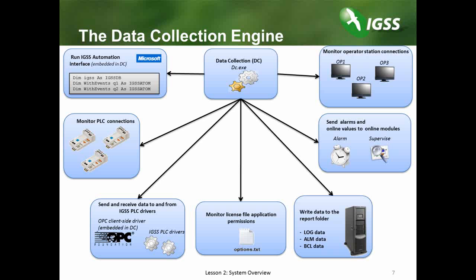The data collection engine. One of the most important engines in IGSS is the data collection engine, often abbreviated DC. The data collection engine is unique to the IGSS system and is a central part of the IGSS software product, enabling the online monitoring and control necessary for the system. The DC engine sends changes that occur in the process to operator stations where personnel monitor and control the system. It also processes and sends alarms and online values to online modules such as the alarm module and the supervise module. It is also the function of the DC engine to collect and write data to the report folders, including log data, alarm data, and base class data, or BCL.